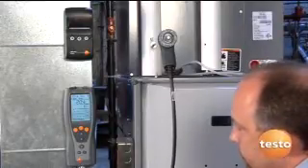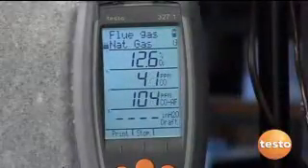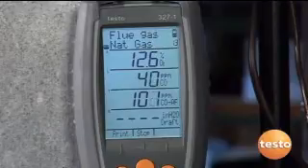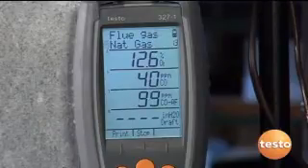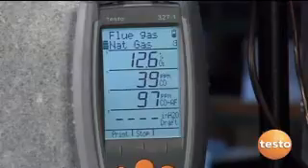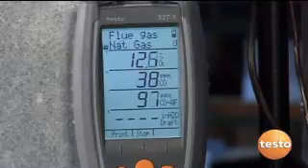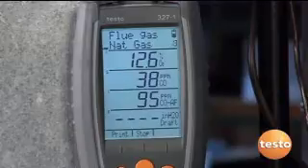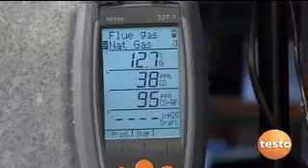We want to do a pre-test to make sure the unit is operating safely before we make any adjustments to the appliance. When the system powers up we're going to watch the CO and the CO air-free readings. Typically we want to see the CO air-free under 400 parts per million when the furnace lights off and during operation. We're watching CO to protect the cell, but any time the CO reading gets over 1000 parts per million you should probably pull the probe from the stack.